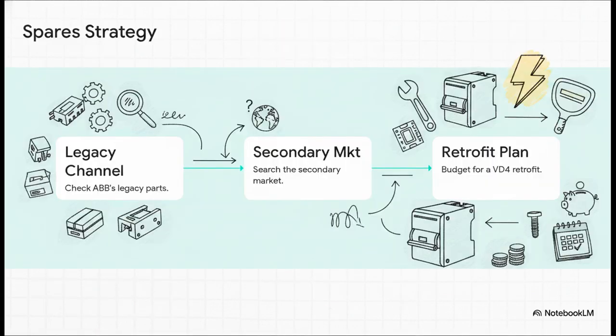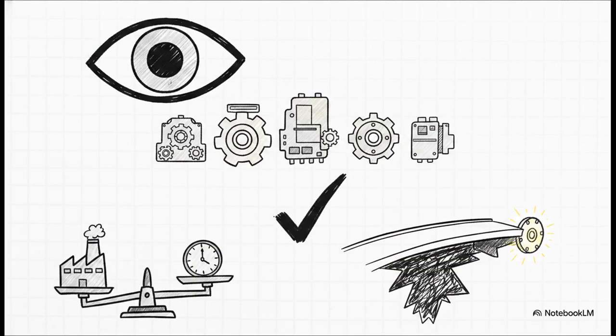This brilliantly illustrates why you absolutely cannot assume indefinite spare support. Your realistic plan requires a serious pivot. First, you check ABB's legacy parts channel to see if there's any remnant stock floating around. Second, you start scouring the secondary market. But the most critical step: you immediately start budgeting and planning for an eventual VD4 vacuum retrofit. The end game for a legacy breaker is always a modern upgrade. The second you spot that obsolete tag, your whole strategy has to shift so you can guarantee the long-term reliability of that vessel.